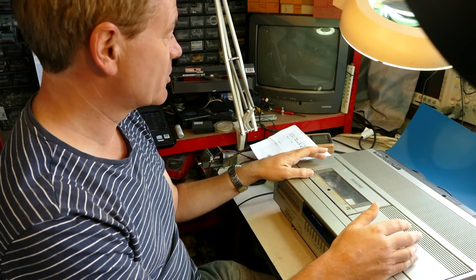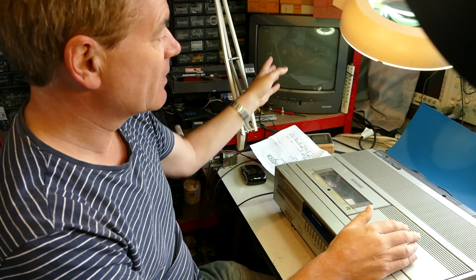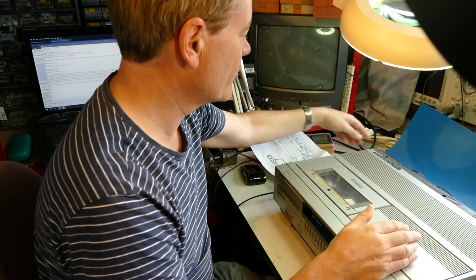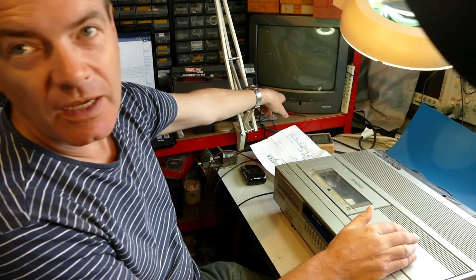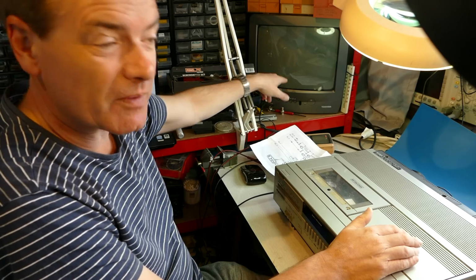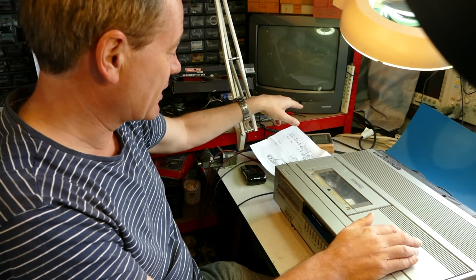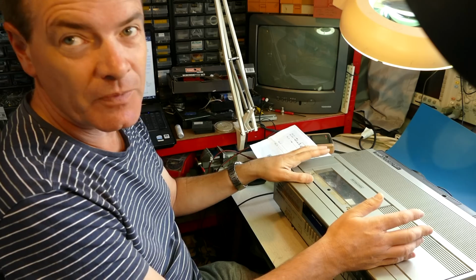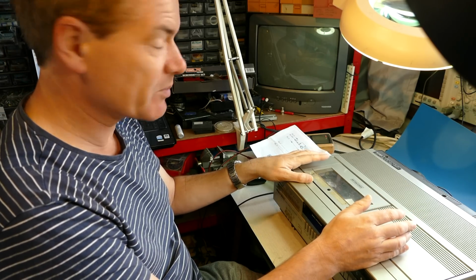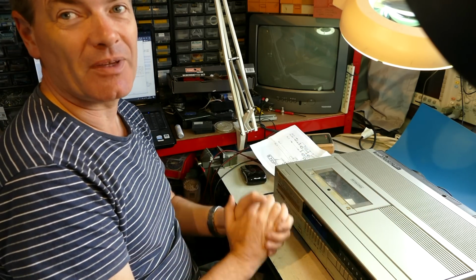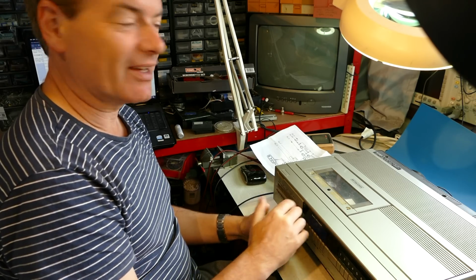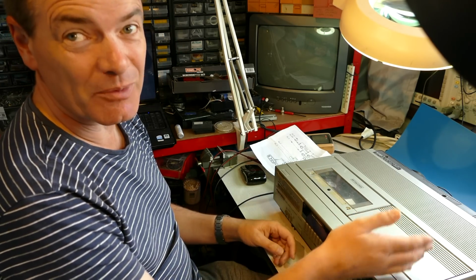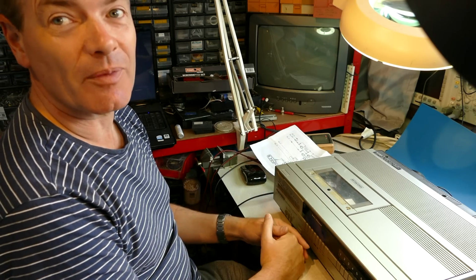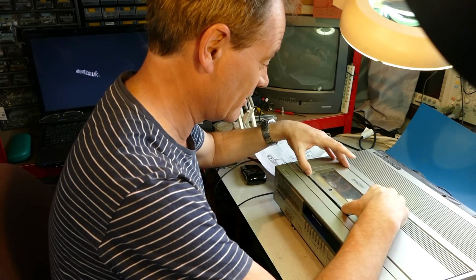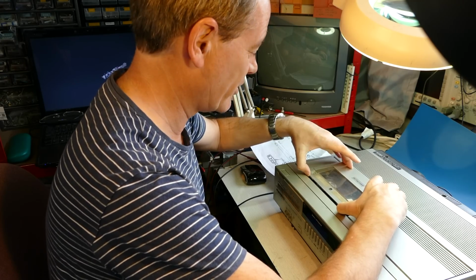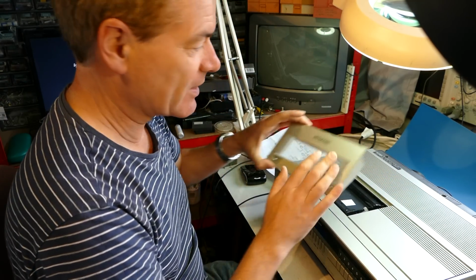That capacitor is designed to stop, I believe, the output side of the power supply drifting up in terms of high voltage, but the risk is that it tends to feed back through the connectors something like half mains potential at very low current. If you're not expecting it and you're connected to something that's not earthed, you can get yourself a small shock. Once upon a time I was up a satellite dish in the pouring rain, and the satellite receiver was plugged into a TV that was in standby, and I got a shock up on the top of the ladder, and I wasn't impressed. So, take that off.